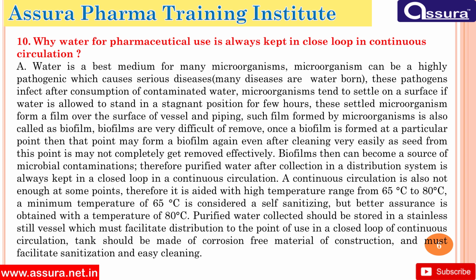80 degrees Celsius. Purified water collected should be stored in a stainless steel vessel, which must facilitate distribution to the point of use in a closed loop of continuous circulation. The tank should be made of corrosion-free material of construction and must facilitate sanitization and easy cleaning.